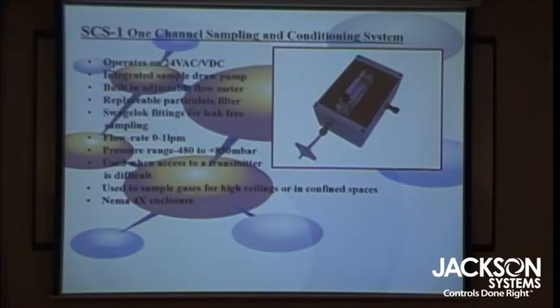We also have sample pumps. You may find out, if you're dealing with natural gas or ammonia, it may be really inconvenient to place a sensor 50 feet up a tower or something. So climbing up a ladder for that is inconvenient. And consequently, you may have a trench where propane may accumulate. If you place a sensor in there, you have a chance of flooding and you'll ruin the sensor. So by having a pump, you place that on the wall and you run a tube up to where your sampling point is. It'll draw the sample in, and then we can push it into the sensor.